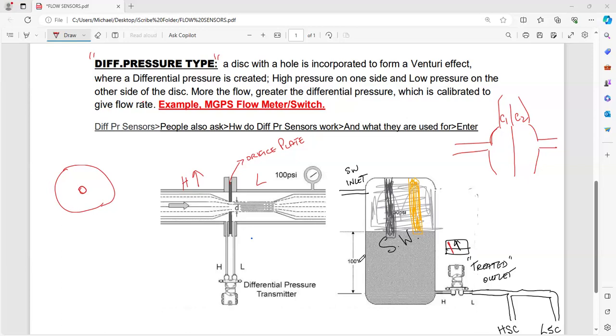A student asks about the auxiliary boiler's DP transmitters. The instructor clarifies that the differential pressure transmitter discussed earlier was about the pressure in the boiler drum, where steam and water levels affect the low and high pressure sides. That was not about flow, but pure pressure.